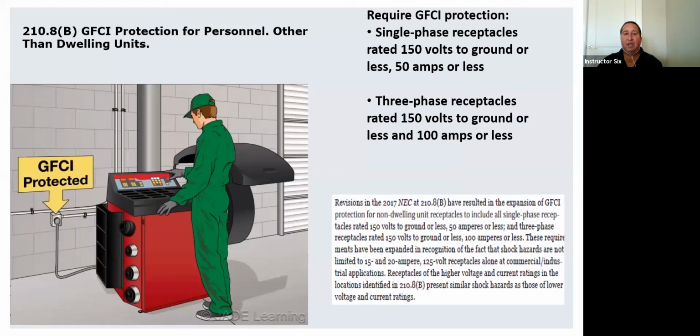210.8(B), GFCI required in commercial, 3-phase receptacles, 150 volts or less, and also 100 amps or less. So if you're working in a mechanic's place or something, and they have a machine like this, now it has to be all GFCI protected. All single-phase receptacles have to now be GFCI protected.